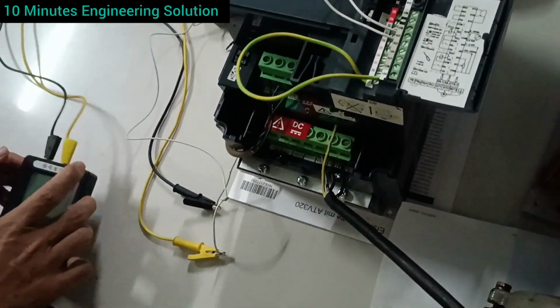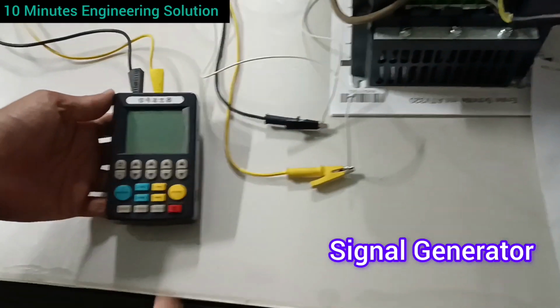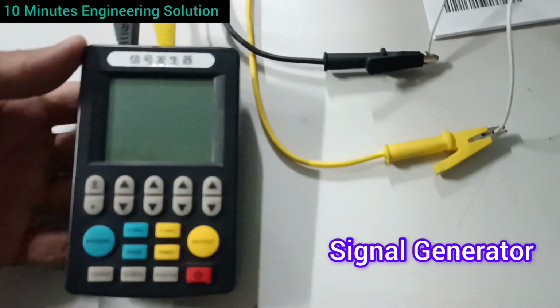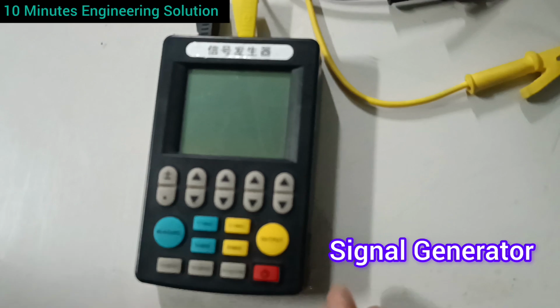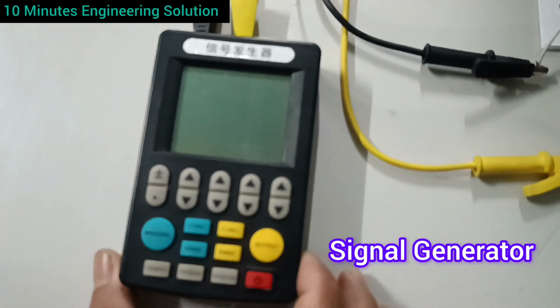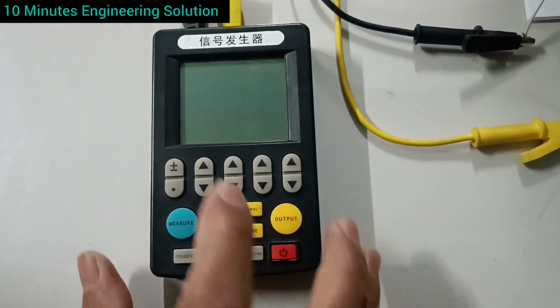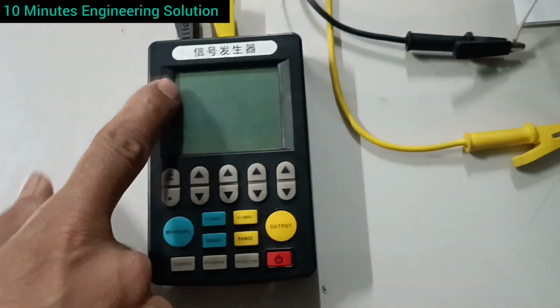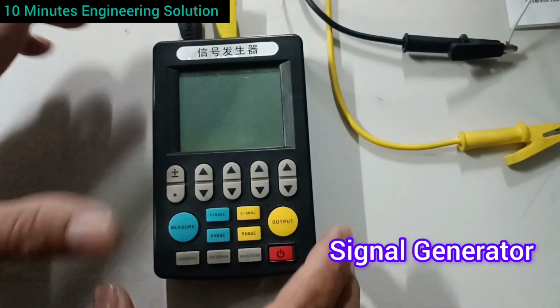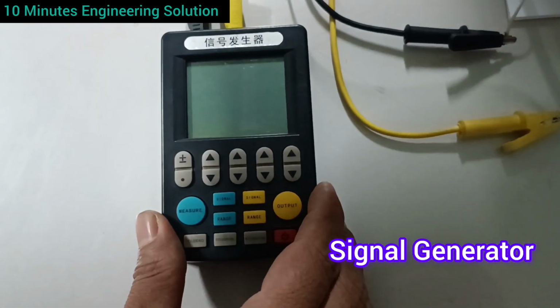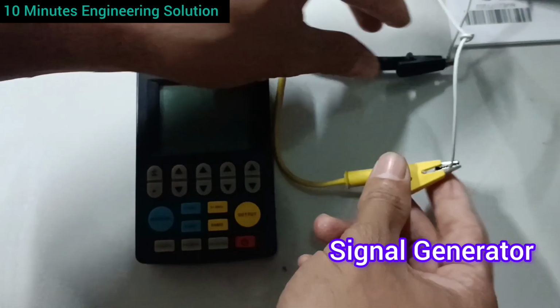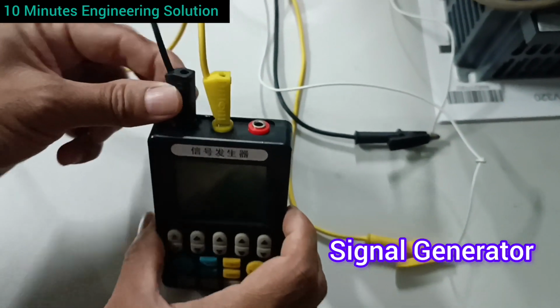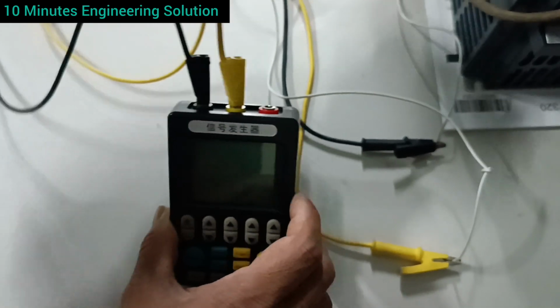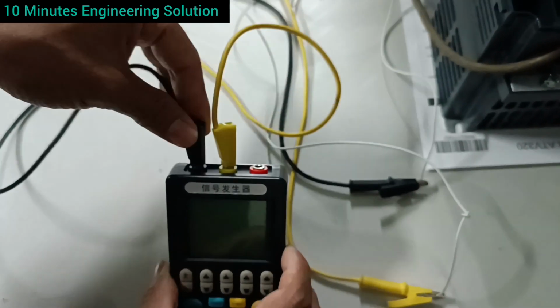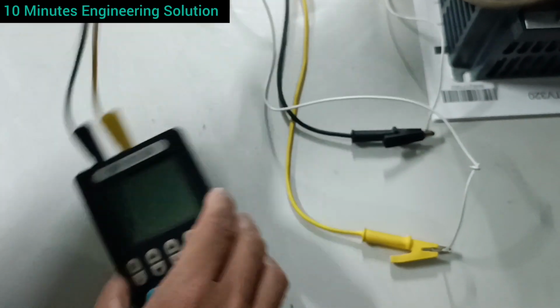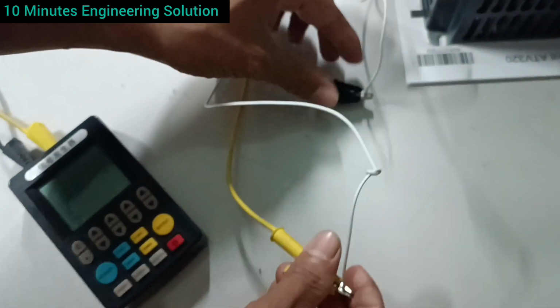Now I'm going to give the analog signal. You can see the picture here. This is the signal generator. A signal generator means we can generate 4-20 milliampere from this device, 0 to 10 volt, and 0 to 20 milliampere also. We can also measure 4-20 milliampere and 0 to 10 volt. I have no field device here, so this is the common connection and this is the positive connection. So I'm using the signal generator to give the VFD a 4 to 20 milliampere signal for test purposes.